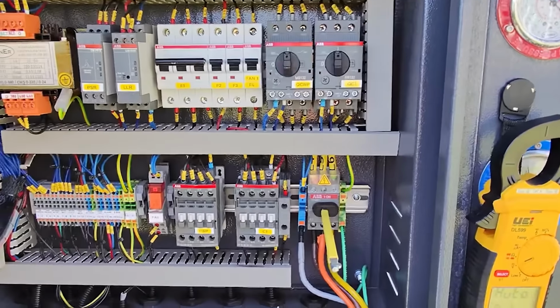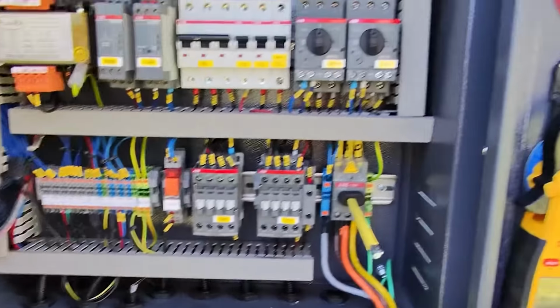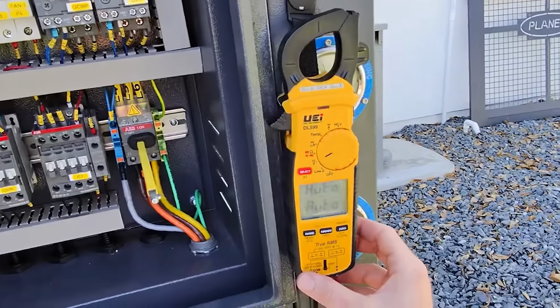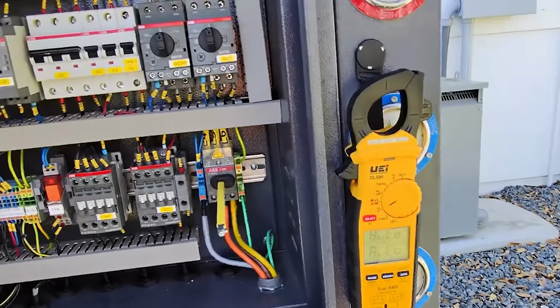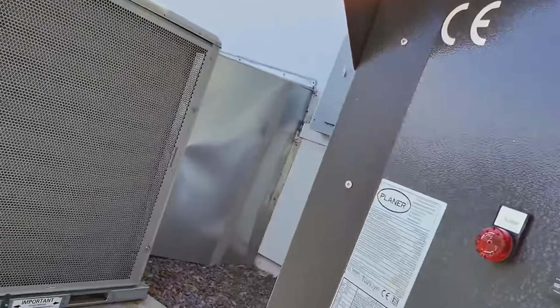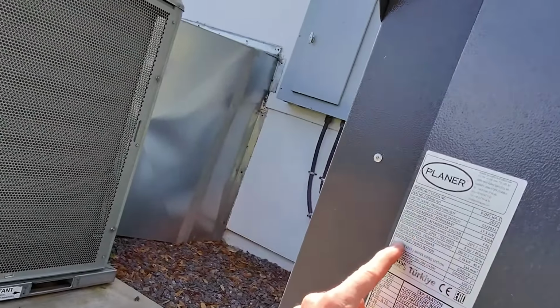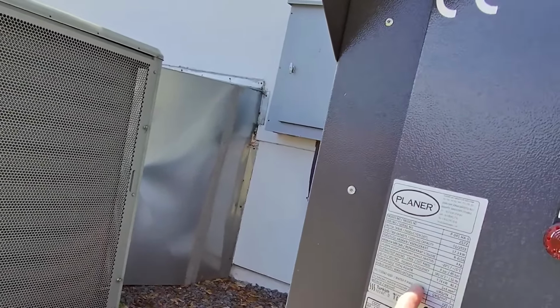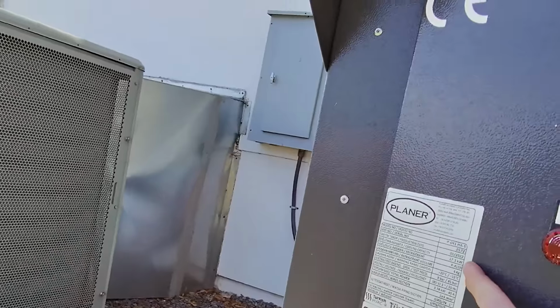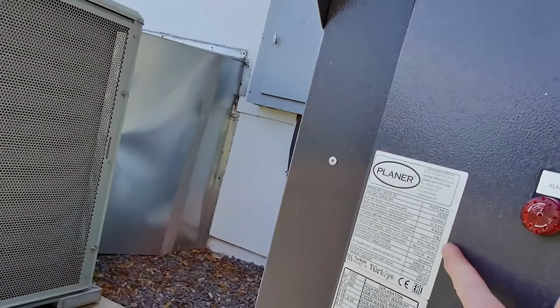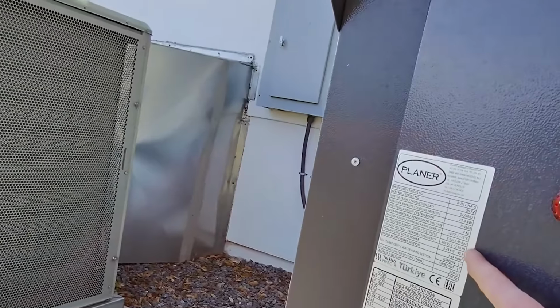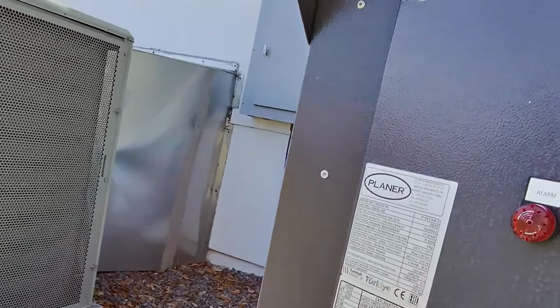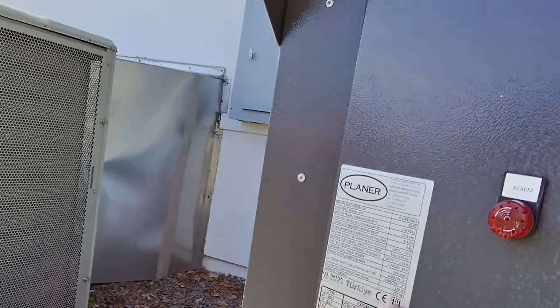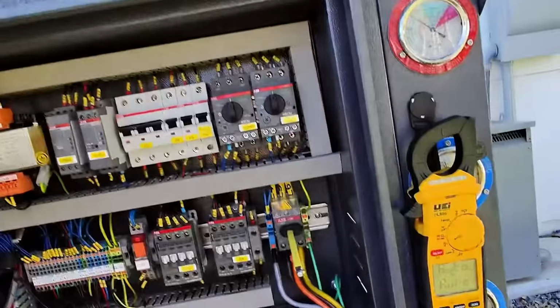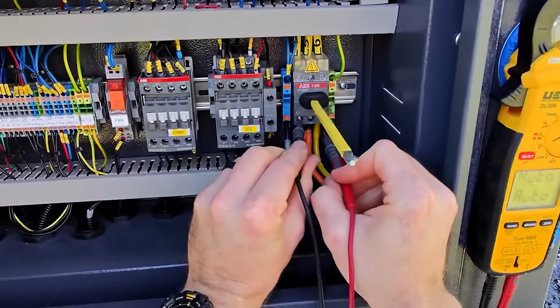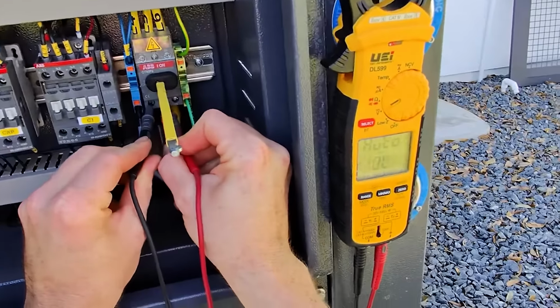So something I skipped over, just because I'm excited to see new things and I love to fix things that are broken that I've never learned anything about, is testing voltage. So we've got a system that you're going to notice here is actually in German for most of the naming, translated to English here, and you'll notice our power rating, cooling capacity, kilowatts here, right? Our pressures are in bar, 380 volt, 50 hertz, so none of this stuff is for our North American market here. And so what we should be doing is verifying the voltage that we have coming to this unit.